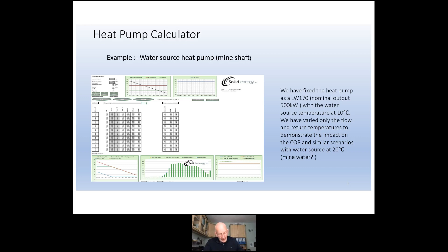What I want to show today is the impact of high flow and return temperatures on the efficiency of heat pumps. This slide here shows that the red line is the heat output of the heat pump. The green line is the electrical input. The blue line, which falls as the temperature rises, is the heat demand from the system.